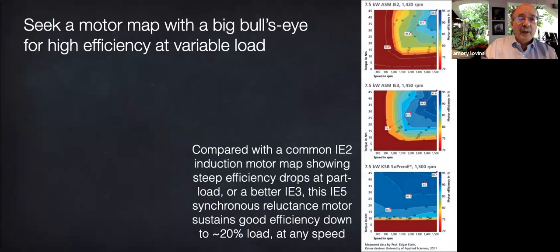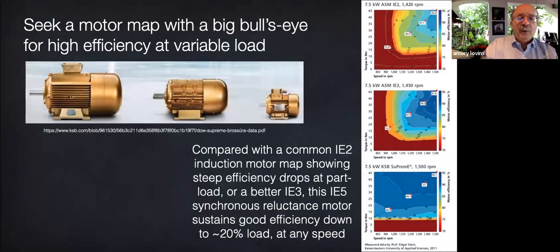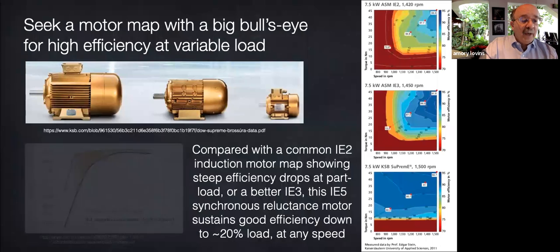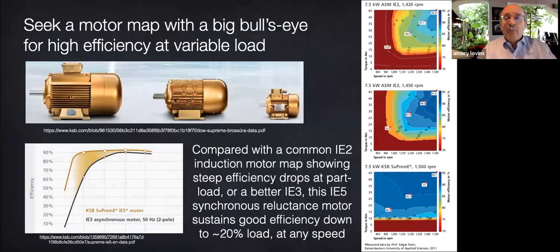or 10 horsepower IE2 or IE3 motor, the highest efficiency is limited to the small or medium-sized bullseye in the upper right of the motor map of torque versus speed at the upper right corner of this slide. So you see that little dark blue zone, that's the bullseye. But this German line of reluctance motors offers high efficiency all the way down to about 20% load running at any speed. The gold zone in the lower left graph shows the energy savable at part load by running the 7.5 kilowatt model rather than a normal IE3 motor like the one in the middle map on the right. And the advantage can easily be 10 or 20 percentage points beyond the roughly 5 points you would expect just from going to this IE5 reluctance motor.